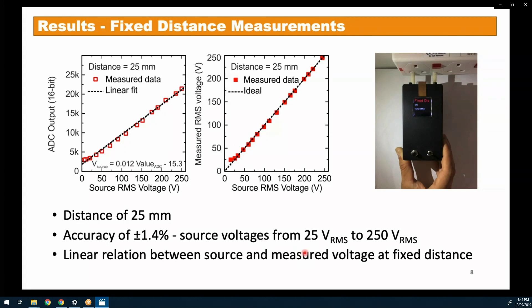On the right hand side, we have run a new measurement where we again change the source voltage from 25 to 250 volt RMS, and then we recorded what our calibrated voltmeter is giving us. And as you can see, we've achieved plus minus 1.4% accuracy. Again, pretty linear. That's not surprising. And it's been calibrated for source voltages between 25 to 250 volts.